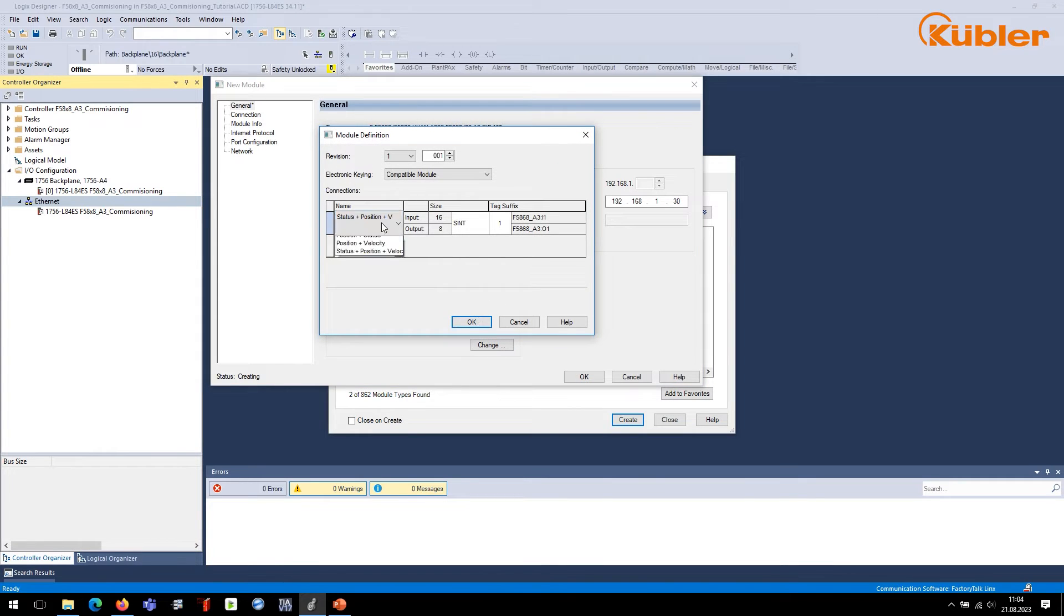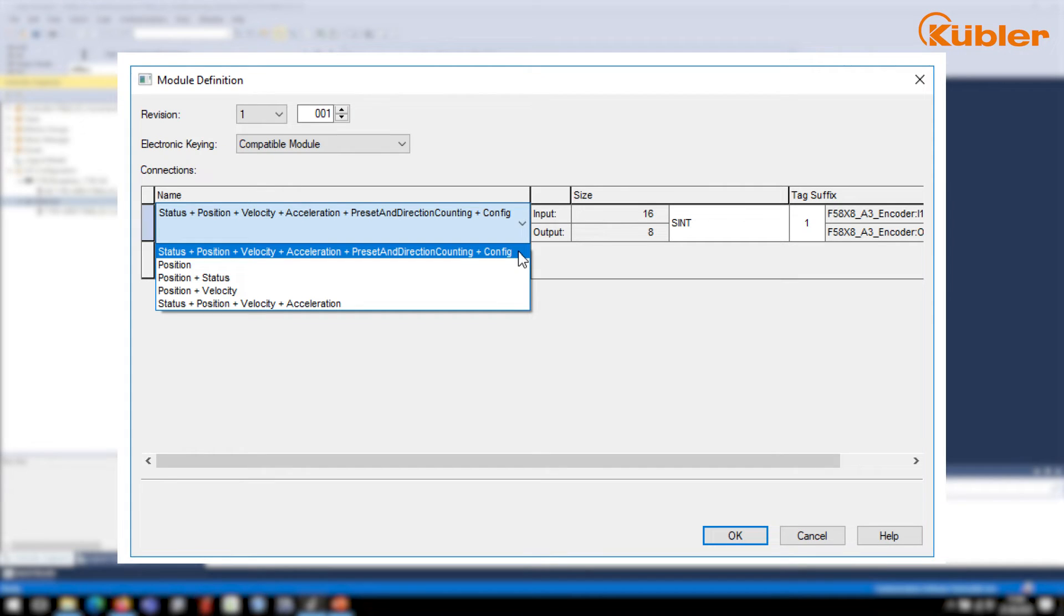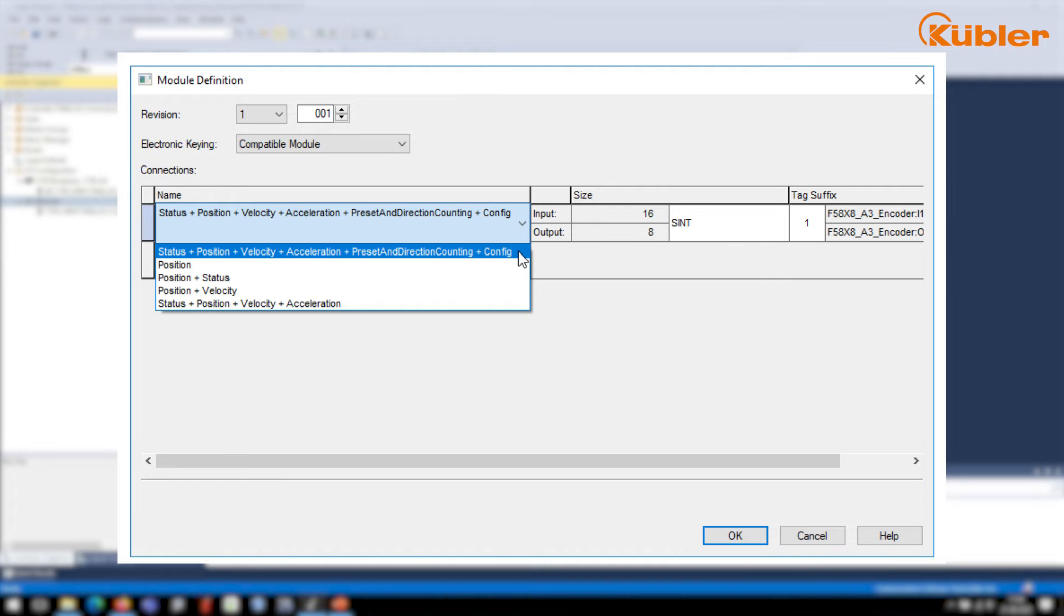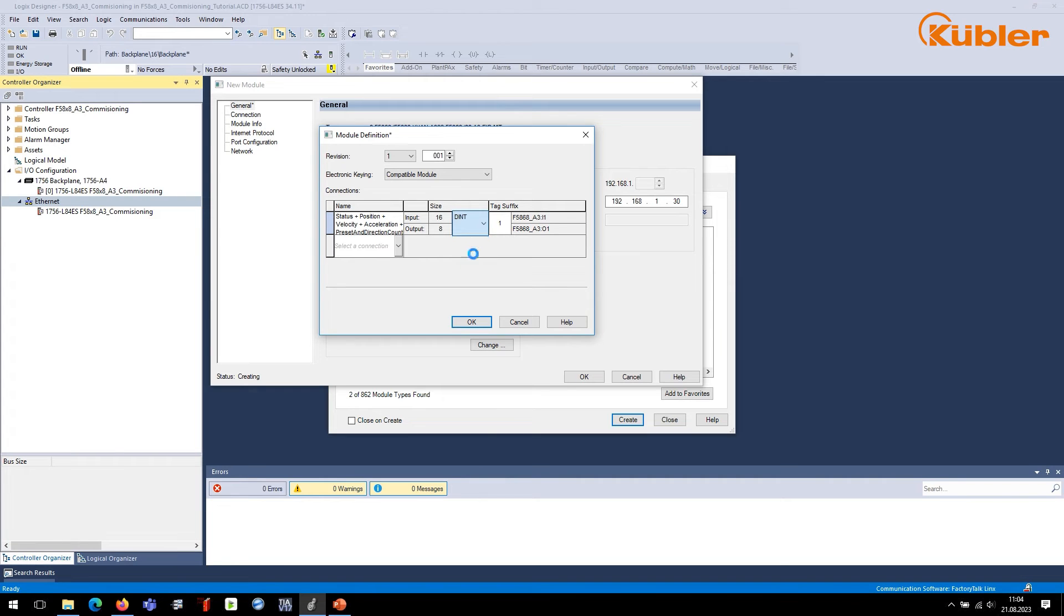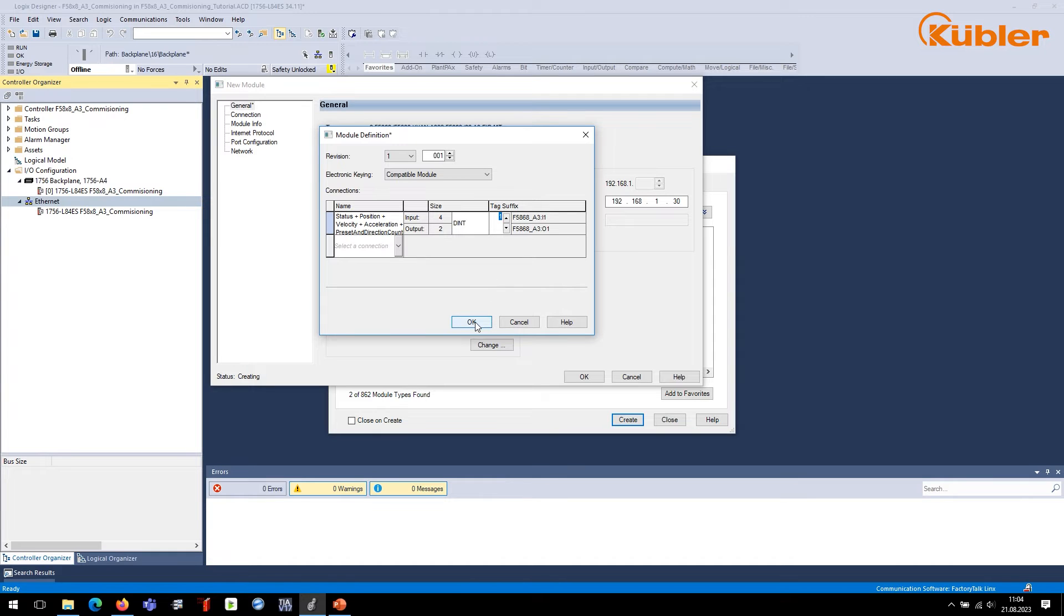Select your desired connection. For this example, use the default connection Status plus Position plus Velocity plus Acceleration plus Preset and Direction Counting plus Config. Select Data Length. With the data type double int, all encoder inputs are displayed correctly as all input instances are 4-byte.